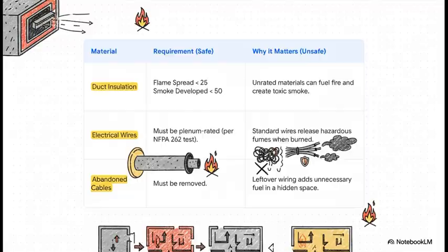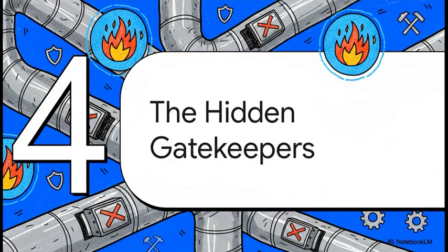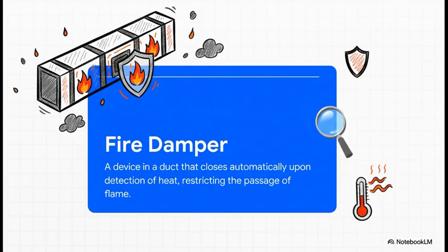Okay, so we've covered the materials, but what about active protection? What happens when a duct has to go right through a solid, fire-rated wall designed to stop a fire from spreading? You install one of these — a fire damper. Think of it like an automatic guillotine, a hidden gatekeeper sitting inside the ductwork. Its one job is to slam shut in a fire, and when it does, it effectively rebuilds that fire-rated wall right through the duct.